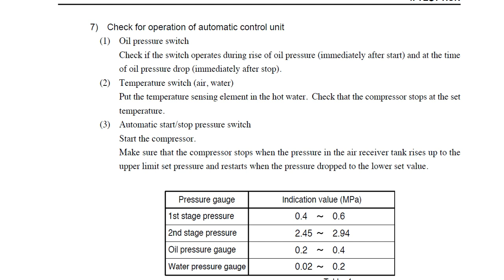The compressor must stop when the pressure rises in the air receiver tank, air bottle—different names we have on board—or main air reservoirs. At the upper limit that we have set, it must be stopped, and it restarts again when the pressure drops to the lower set value.